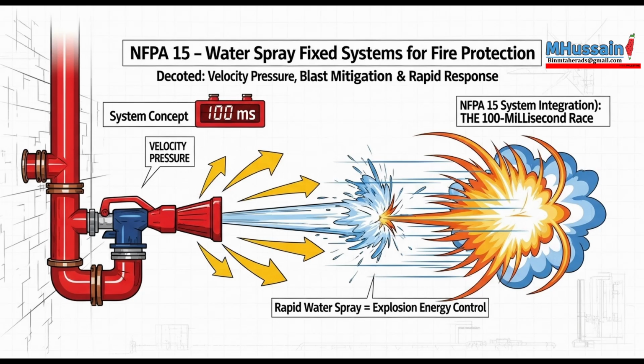You also have to rigorously check the lightweight pipe's beam strength. That dictates your hanger spacing, your support needs. If you space hangers too far apart, the pipe could sag. And even a slight sag could disrupt the precise trajectory of a spray nozzle. In a system designed for precision, that's potentially disastrous. The engineer has to consider movement, vibration, temperature swings, and just the sheer dynamic shock when a massive deluge system kicks on. You have to ensure that movement doesn't compromise the structure or nozzle performance.